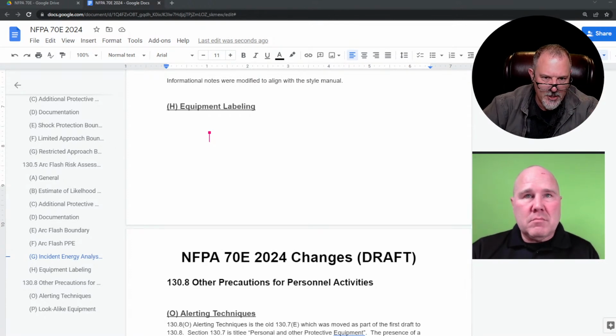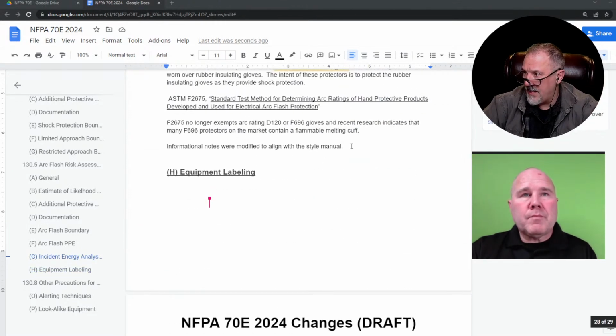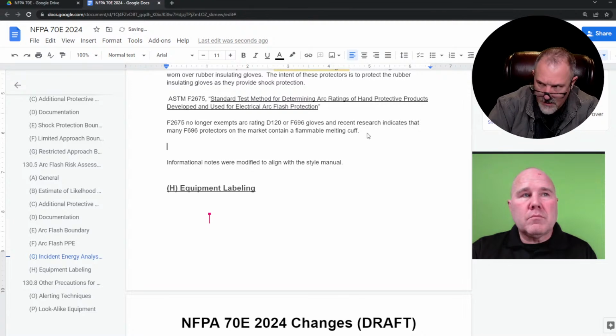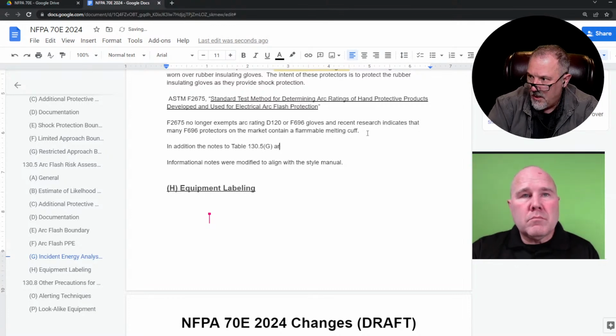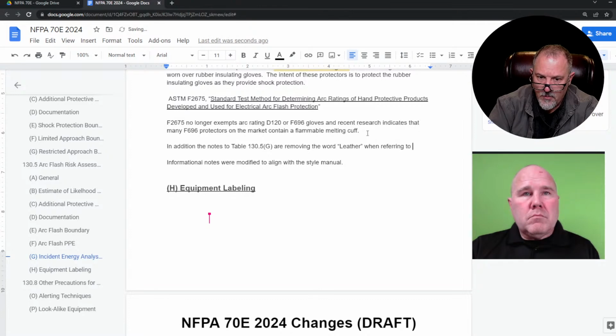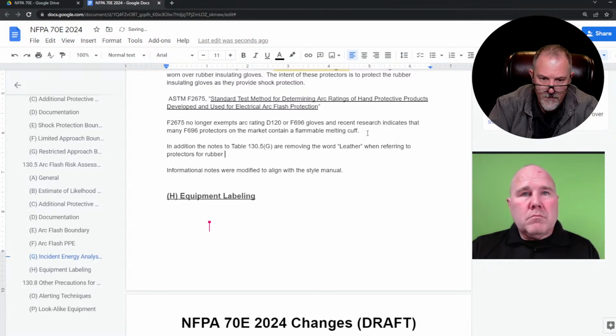We got changes. We got a new informational note just reminding us that changes can increase or decrease. We have modifications to the informational notes. We're removing leather from the protectors, and we're just saying protectors. We have a new definition of protectors. They removed where it says rubber insulating gloves with leather protectors provide arc flash protection, removing the word leather. So those are the notes to table 130.5G. I will put that: in addition, the notes to table 130.5G are removing the word leather when referring to protectors for rubber insulating gloves.